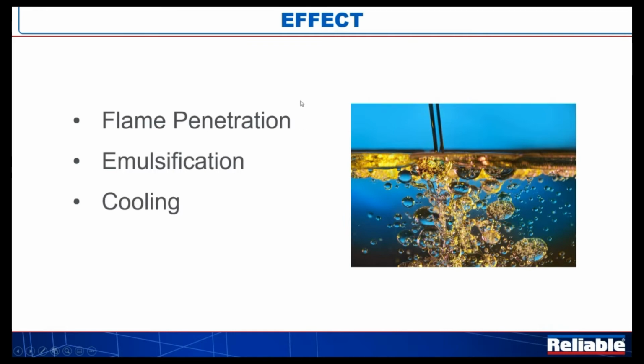There's some cooling effect from the drops, but we're going to see how the medium velocity nozzle has an even better way of doing that. And then finally, there is some smothering effect. But the main concept of the high velocity nozzle is that coarse water drop, flame and fire plume penetration down to the surface, boil that water. Maybe that's the wrong word for it, but let's activate that water and get the oils and the water mixing, the fuel and the water mixing, to affect the firefighting process.